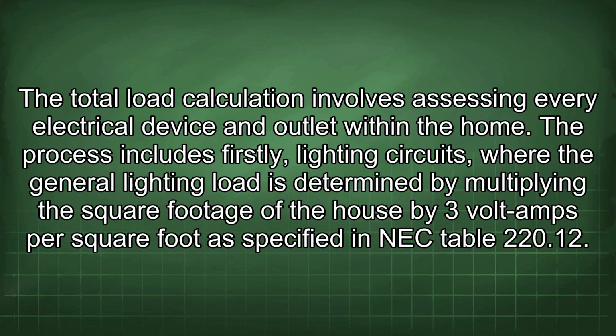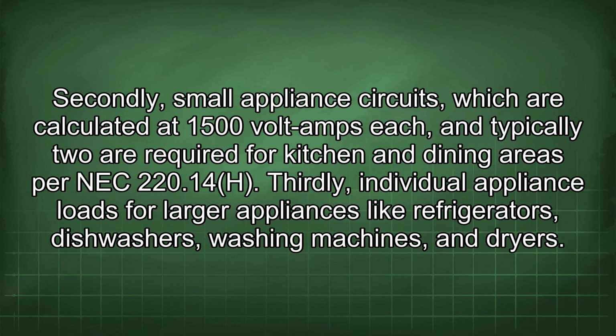The total load calculation involves assessing every electrical device and outlet within the home. The process includes, firstly, lighting circuits, where the general lighting load is determined by multiplying the square footage of the house by 3 volt amps per square foot as specified in NEC Table 220.12.